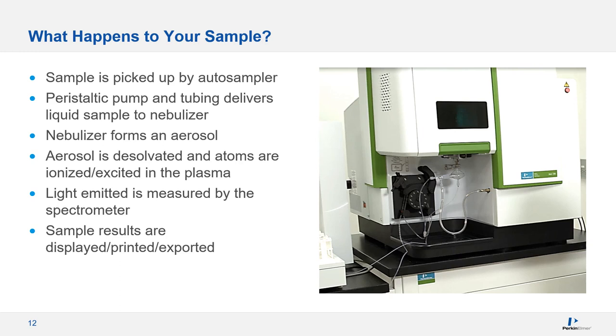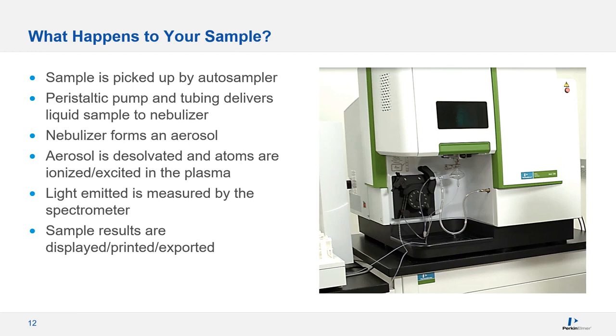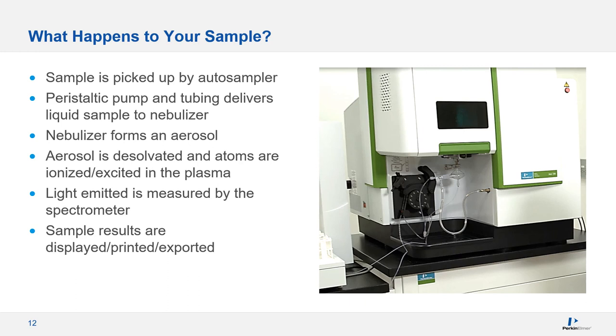The standard ICP-OES analysis process looks something like this. The liquid sample is picked up by an autosampler. Then the peristaltic pump and associated tubing delivers that sample to your nebulizer, which converts the sample to an aerosol using a stream of argon called the nebulizer gas. The spray chamber separates out the smallest droplets and sends them to the plasma where they're desolvated. The plasma then vaporizes and ionizes the analytes, and that ionization process gives off light at certain wavelengths specific to each analyte. The amount of light emitted is proportional to the concentration of the analyte, so once you've calibrated your spectrometer, it can use those measurements to report a concentration.